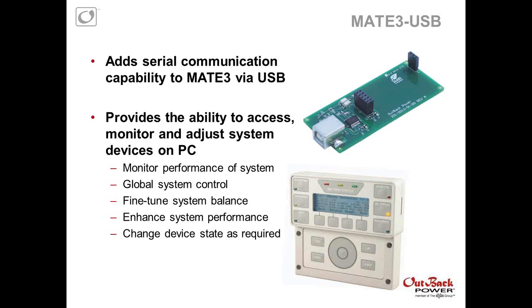And is there monitoring software for the system over the Ethernet now? There is no external software that needs to be provided. The Mate 3 serves its own web page. You can navigate to it from anywhere within the internet or intranet and be able to pull up the screen and see what's happening with the system. No other programs need to be purchased.